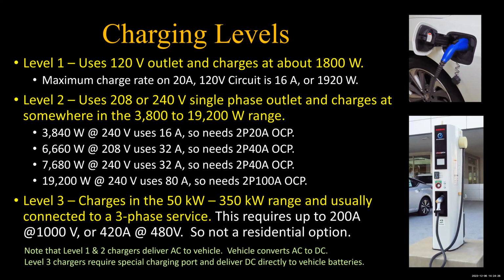And if the vehicle is going to try to send some power back out to the grid upon a request by the grid, it's going to have to change it back to AC again. And most of the vehicles right now don't have the inverters to do that. But the National Electrical Code in Article 625 actually does have a provision that says that if you have an inverter for extracting AC from an electric vehicle, it has to comply with IEEE 1547-2018. So they're anticipating this, so it's coming, and probably does exist in some areas, but just not in my area right now. So there's your charging levels, 3 of them.